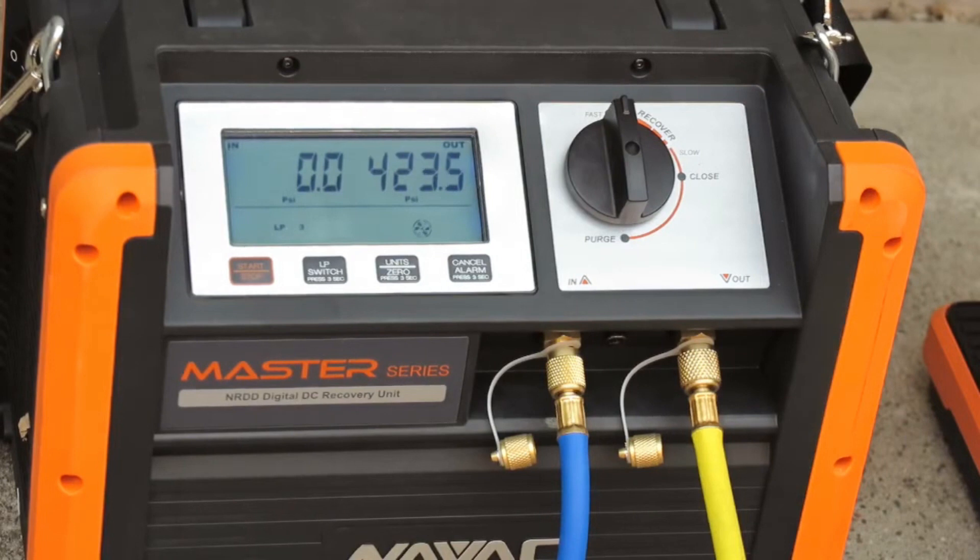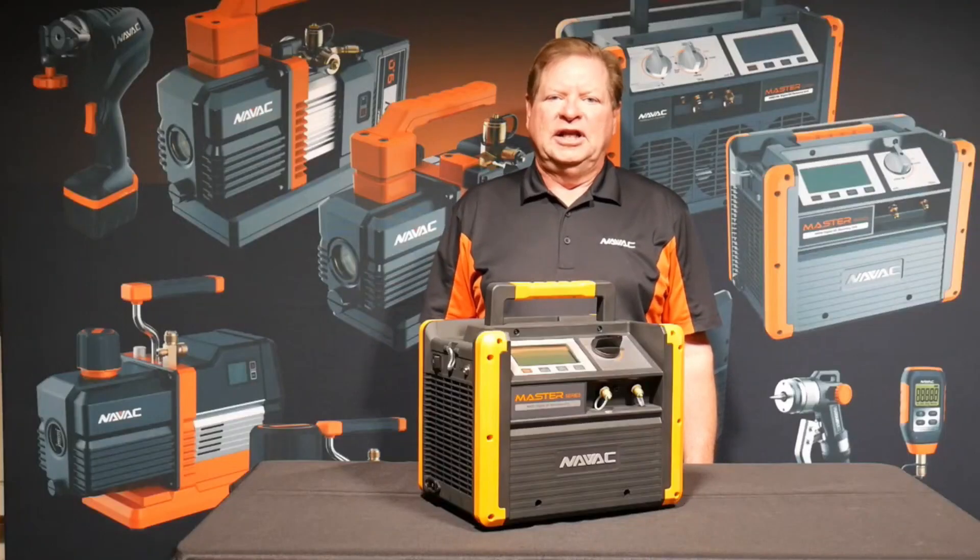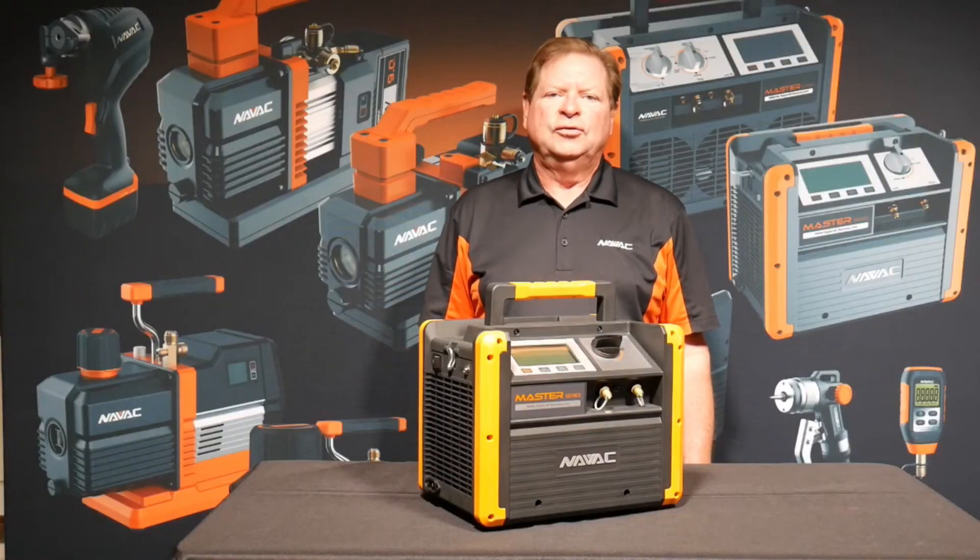After approximately seven minutes, we're down to zero psi — the required recovery level for refrigerant R410A. We've recovered five pounds, four ounces of gas. The system has lost over 40% of its charge. Time to fix the leak, evacuate down to 300 microns, recharge, and get this system cooling again. Thank you very much for spending a few minutes with us, and we at NAVAC Tools hope you have a great day.